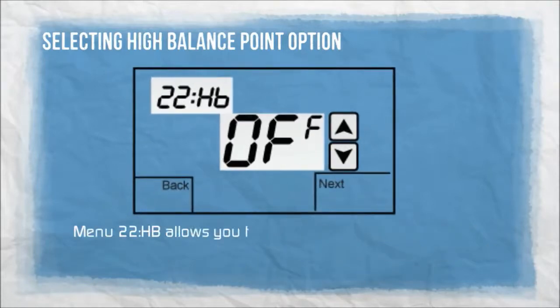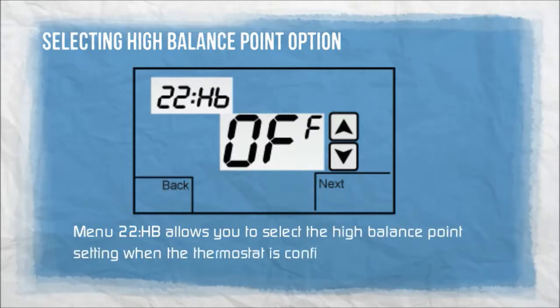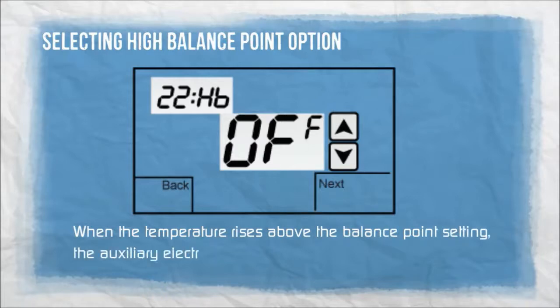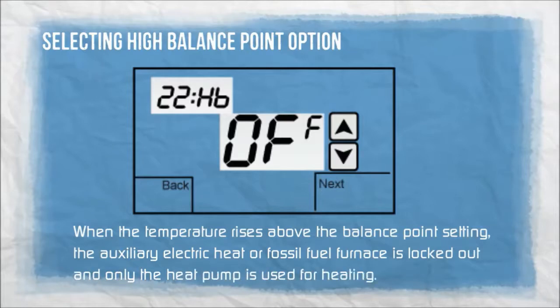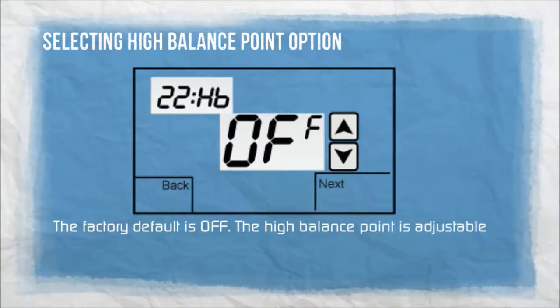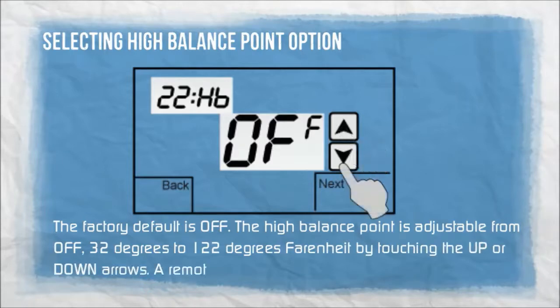Menu 22HB allows you to select the high balance point setting when the thermostat is configured for heat pump or fossil fuel. When the temperature rises above the balance point setting, the auxiliary electric heat or fossil fuel furnace is locked out and only the heat pump is used for heating. The factory default is OFF. The high balance point is adjustable from OFF, 32 degrees to 122 degrees Fahrenheit. A remote outdoor sensor must be installed.